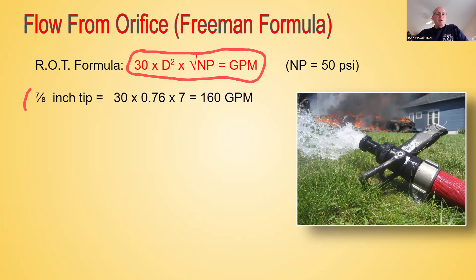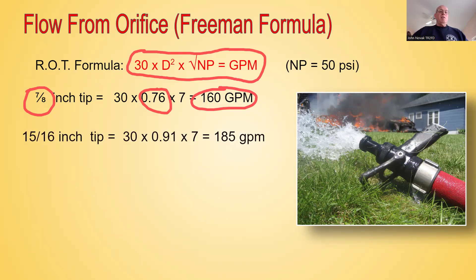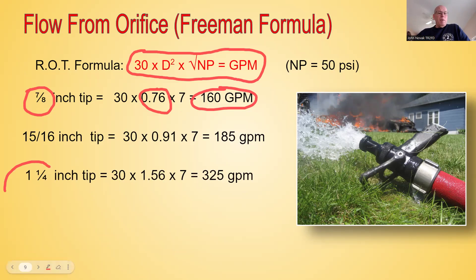With a 7/8-inch tip, we put that into a decimal, square it to get 0.76, do the math, and end up with 160 GPM. With a 15/16-inch tip — another common tip in the fire service — we do the math and come up with 185 GPM. We can do the same thing with an inch and a quarter tip on a two and a half inch line: the diameter squared comes out to 1.56, we multiply that by the square root of the nozzle pressure — the square root of 50 is approximately 7 — and we come up with 325 GPM. That's a standard formula that's been around since the 1800s.